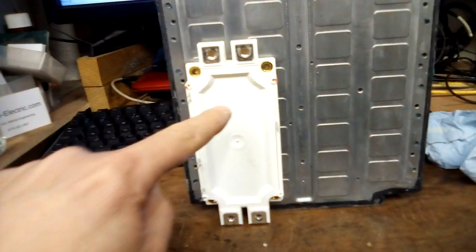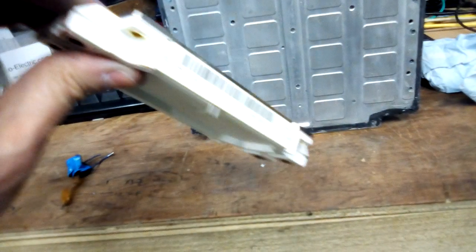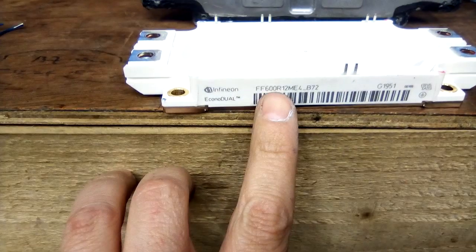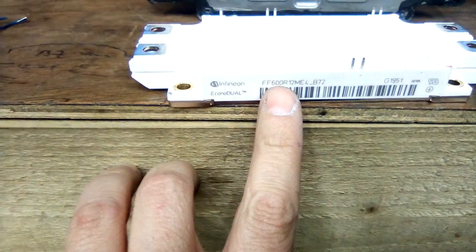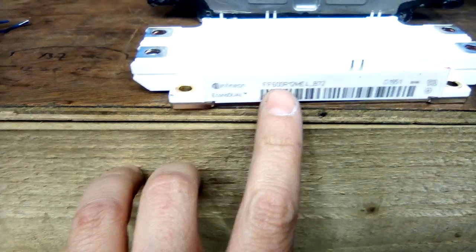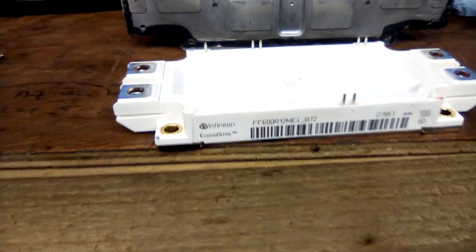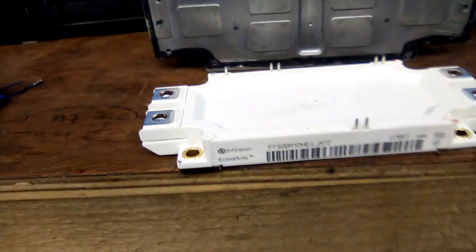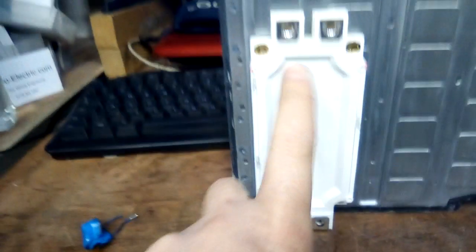This is effectively an equivalent to the original array. This is an IGBT unit with twice the power. You can see it's FF600 R12. The 600 means 600 amps and the 12 means 1.2 kilovolts, 1200 volts. That's how the serial number works.